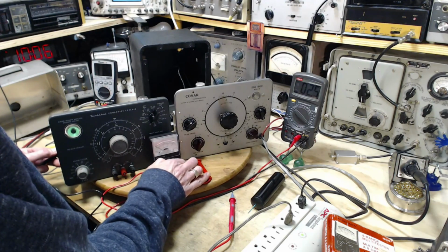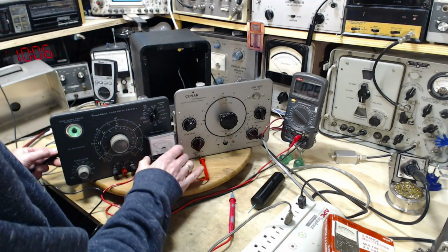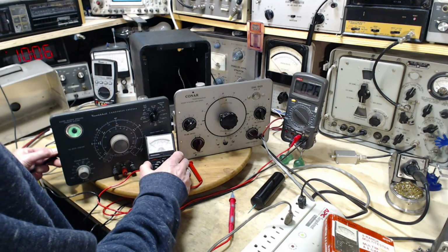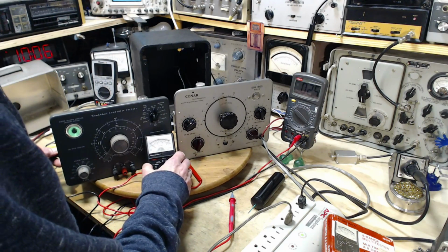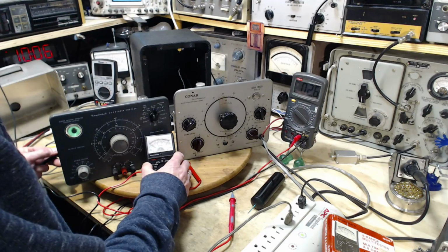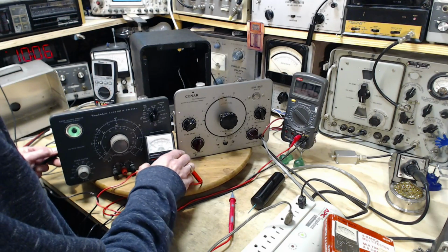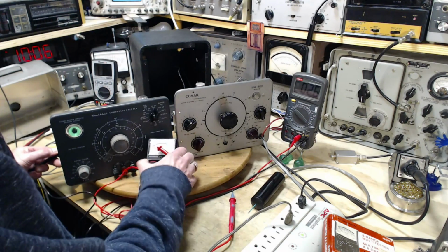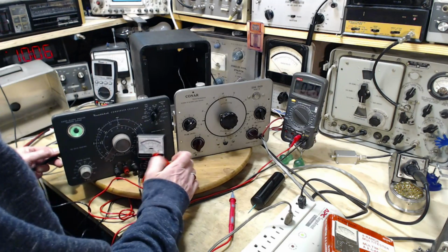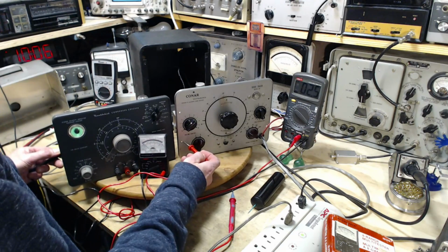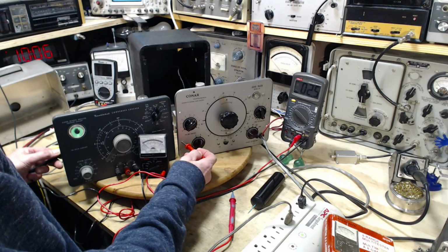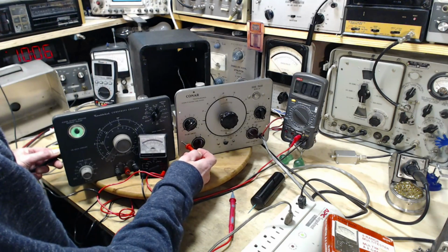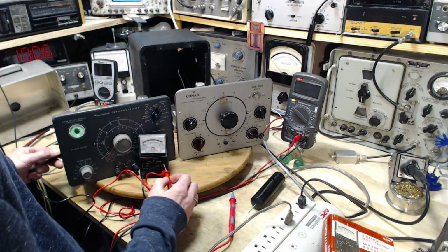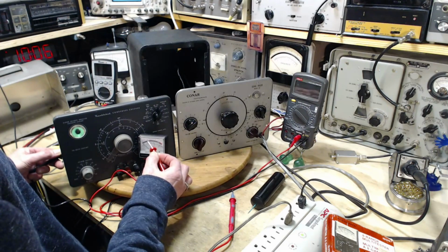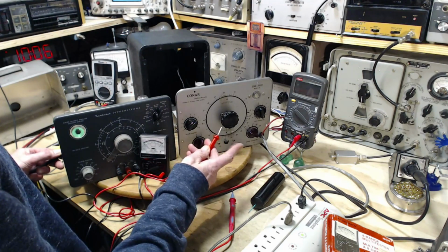Now if we put this on a 150 scale, now it's 150 times 2,000. What's that, 300,000? Times 2,000, 300,000 ohms, so it's not as low as I expected, frankly. I thought it was lower. Well, let's take a look. That's still moving it up. But you're certainly not going to get what it should be coming up to around here. Is going to match that.